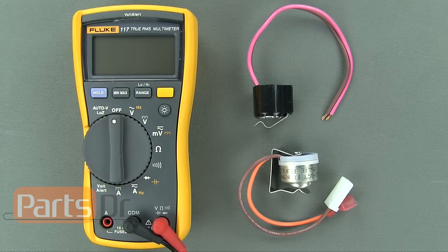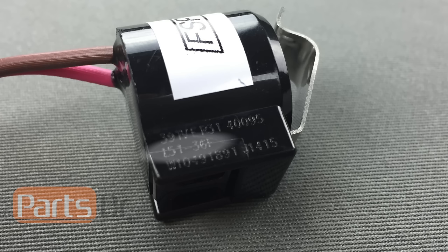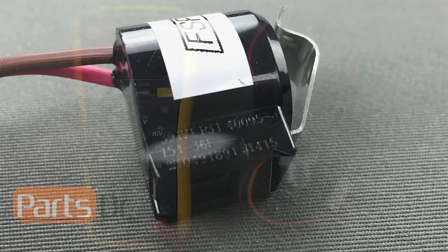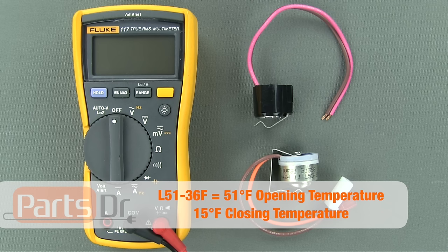Here is another defrost thermostat. This one has a plastic housing instead of metal. This defrost thermostat has L 51 minus 36 F engraved into the side. So this thermostat has an opening temperature of 51 degrees Fahrenheit and a closing temperature of 15 degrees Fahrenheit.